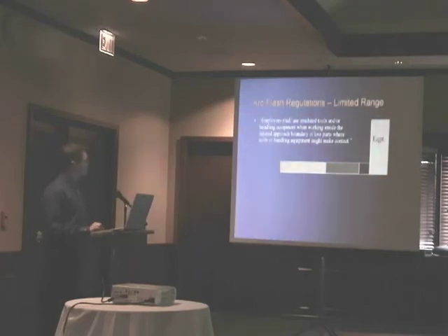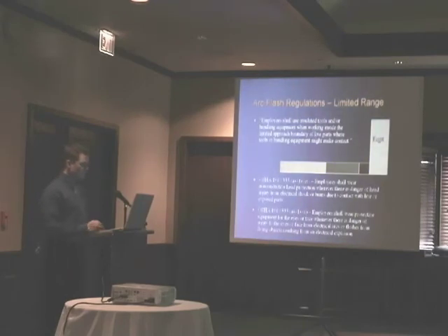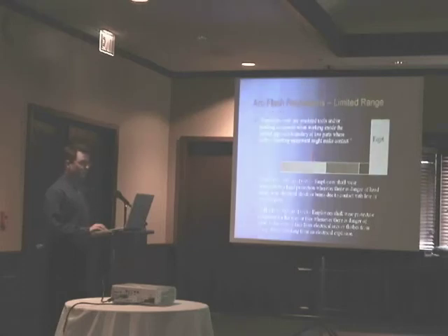Okay, employees shall use insulated tools and/or handling equipment when working inside the limited approach boundary of live parts where tools or handling equipment might make contact. In this OSHA standard, employees shall wear non-conductive head protection where there is a danger of head injury from electrical shock or burns due to contact with live or exposed parts. And they shall wear protective equipment for the eyes and face whenever there is danger of injury to these areas from electrical arcs or flashes or from flying objects resulting in an electrical explosion.